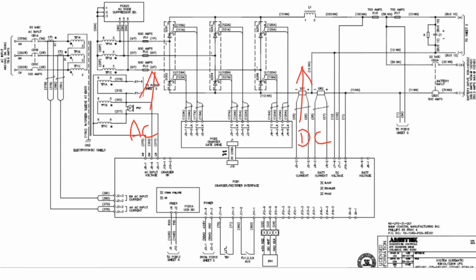Okay, and you can see that we have 2 branches. One, this one up the top here, goes to the inverter, and then this one here goes to our battery. Okay, they are connected in parallel, they're the same points. We want to have this disconnect here going to the battery, and the inverter supply just goes directly to the inverter through those fuses. So that is the charger inside our UPS systems.